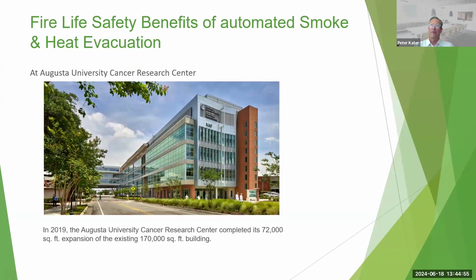Now, I'd like to talk a little bit about the fire life safety benefits. This is with automated smoke and heat evacuation. It's basically the same type of system as we use for natural ventilation. And in fact, as I mentioned before, natural ventilation systems can have this element of fire life safety benefits built into it as well. An example of this would be the Augusta University Cancer Research Center, which is a 72,000 square foot expansion of the existing building. And it uses operable windows and vents to provide smoke and heat evacuation in the event of a fire.